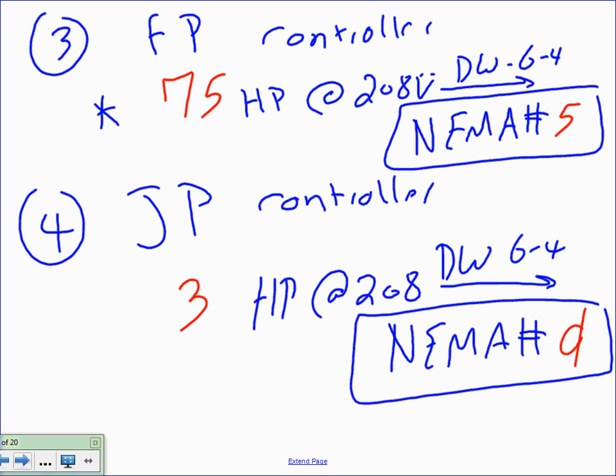Yeah, you probably would put a soft start on that, where you can ramp that thing up when it comes and ramp it down with some control. But VFDs, I've never seen it with a VFD. Soft start is coming, and other auto transformers coming, guys, on these. Or NEMAs, or just across the line NEMAs.